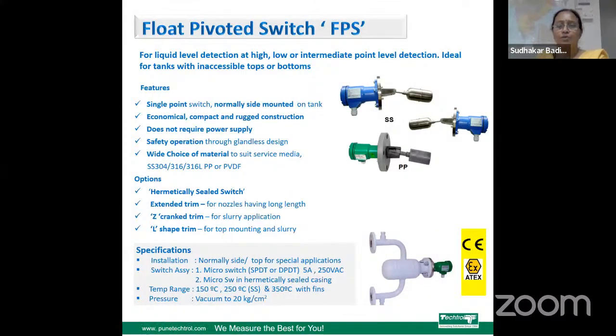Now this is a float pivoted switch. Basically, this is a side mounted switch used for level detection at high, lower, intermediate point levels detection. Ideal for tanks having inaccessible top and bottom. This is a single point switch, economical, compact, and having a rugged construction. This also doesn't require any power supply. It gives safety operation through glandless design.